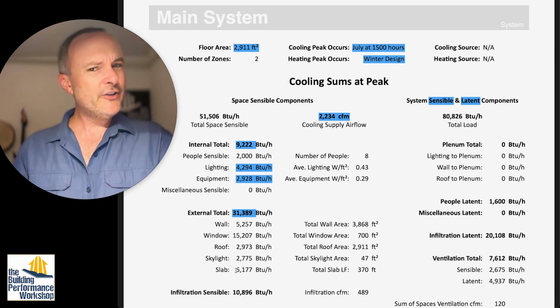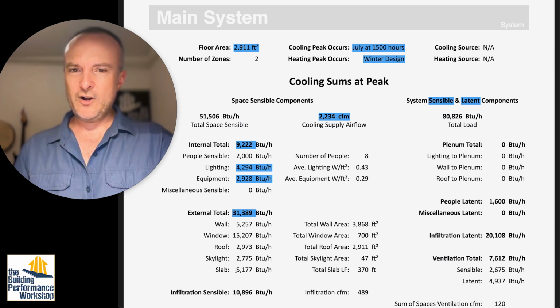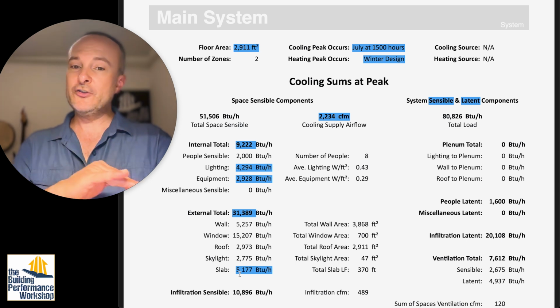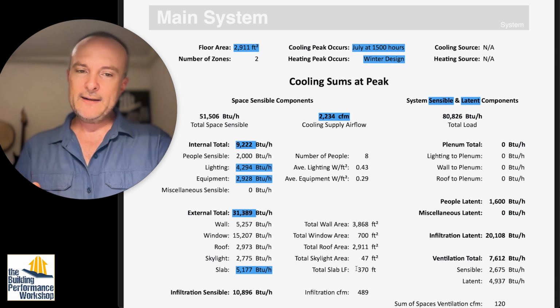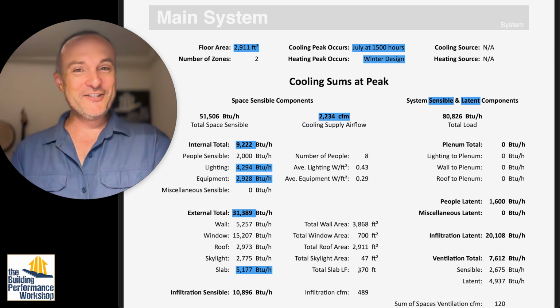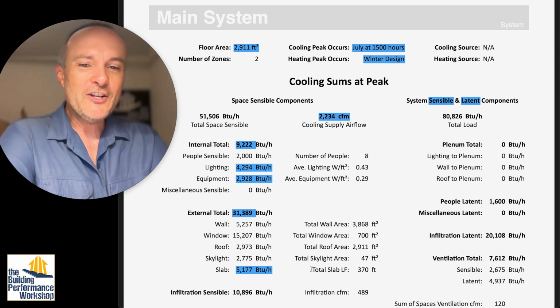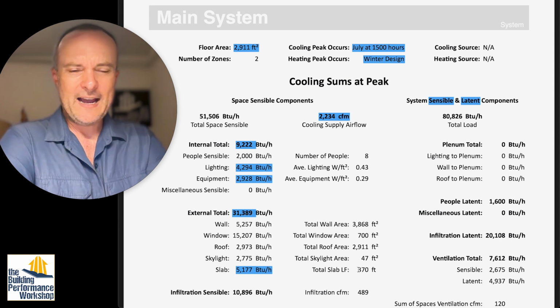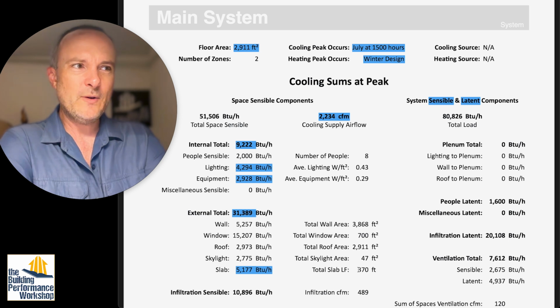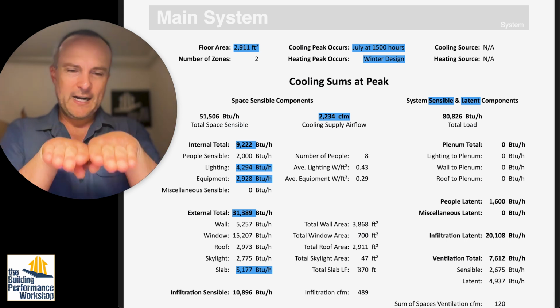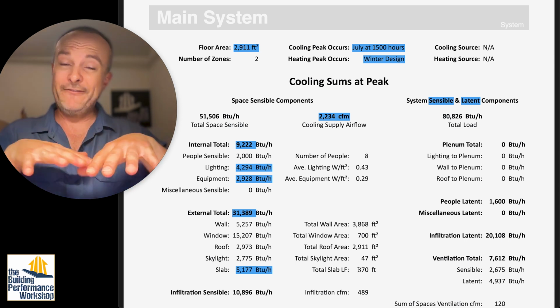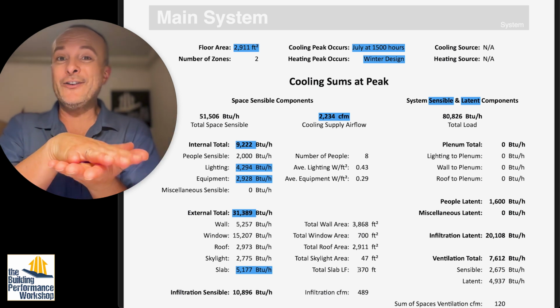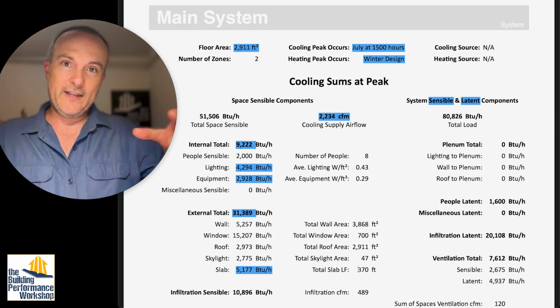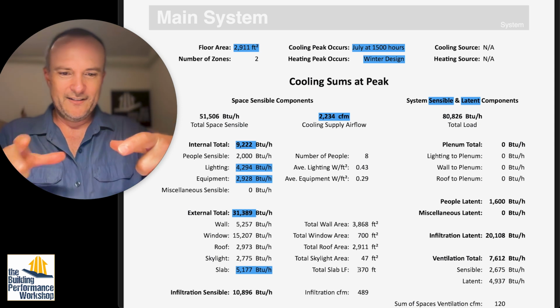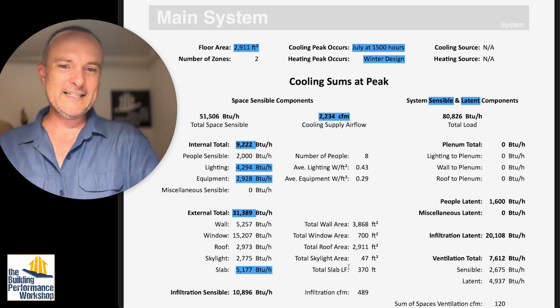And then the slab is also adding to the heat. That's wrong. So this right here, the slab is in contact with the ground. There's no way that that's happening. And part of the reason that that's in here probably, and I'm not an engineer, so if there is an engineer in the audience who wants to say why that's there. The total slab linear footage right here, that's just the perimeter of the slab. So they're saying for some reason, maybe it's because we're in contact with dark asphalt outside and the slab edge is meeting right up with that. They're discounting all of the free cooling that is the heat sink of the slab being in contact with the ground underneath it. And they're saying that the addition of the heat on all sides, because this probably is some little shop in the middle of a giant black parking lot, then that would kind of make sense. But that doesn't really track for me. This is not a residential, once again.